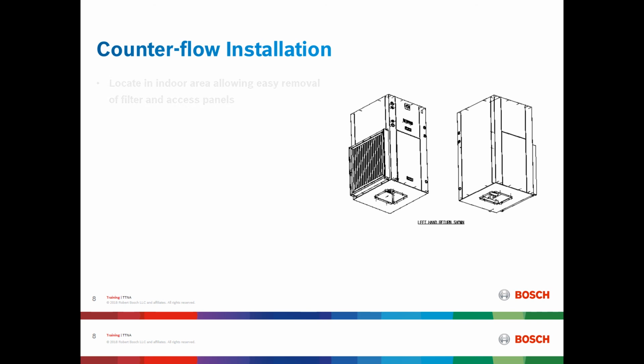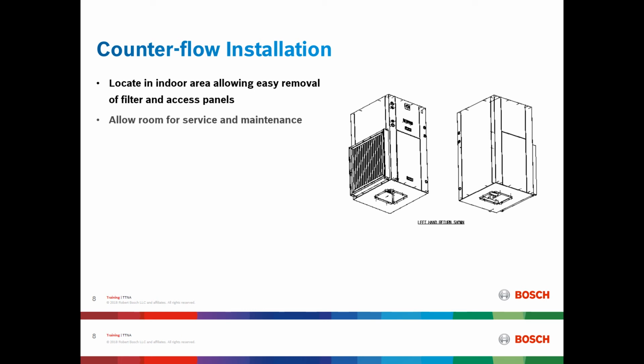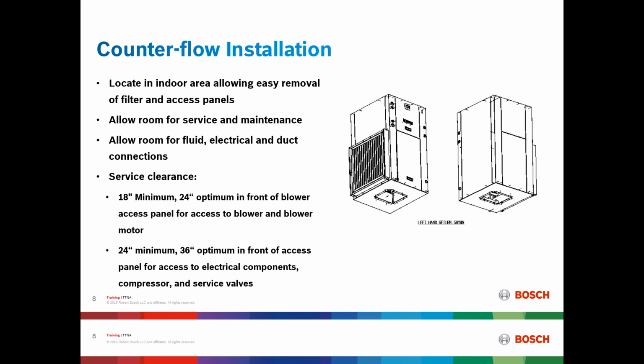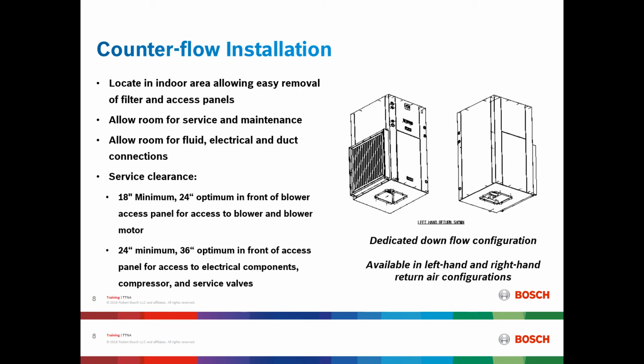For the counterflow application, the unit will still need to be located in an indoor area that is not subject to freezing, that allows for easy removal of filters and access panels, has room for service and maintenance, allows for all fluid, electrical, and duct connections, and also has adequate service clearance. Again, Bosch will provide an installation, operation, and maintenance manual, which will have recommendations for service clearance in it with each unit. The counterflow application has a dedicated downflow configuration. It is also available in left-hand and right-hand return air configurations.